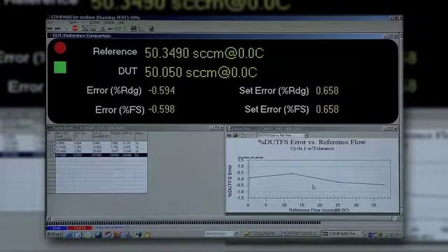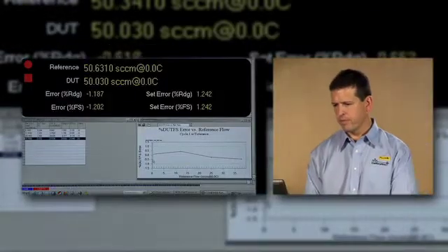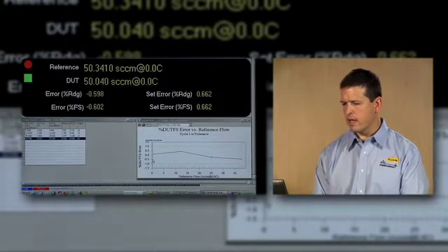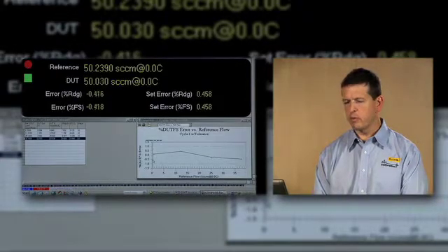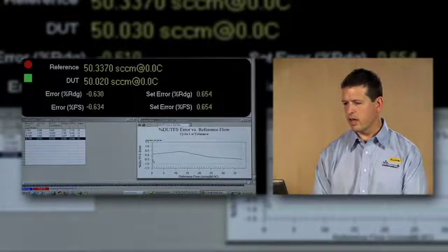On the plot, you can see the 1% tolerance bars are in green, and all of our data so far is within those bars. If we have satisfactory data after running this verification, then we can take the data file and automatically create a report, and the calibration is finished.